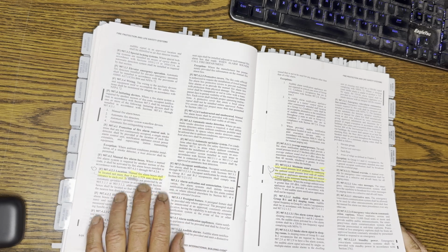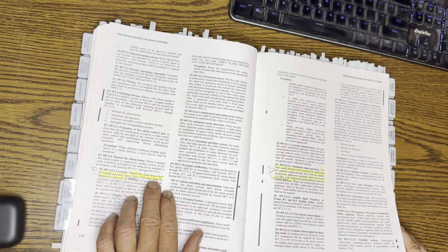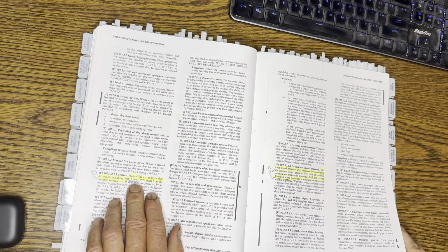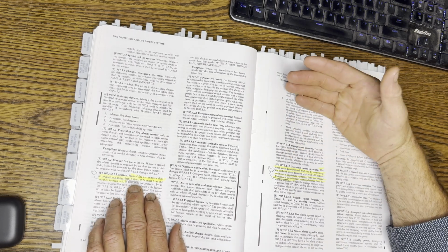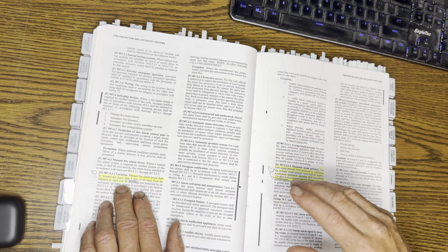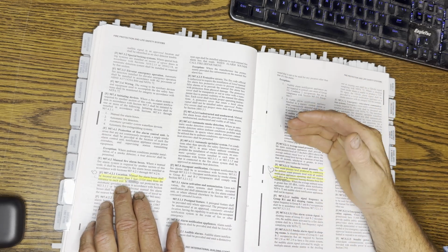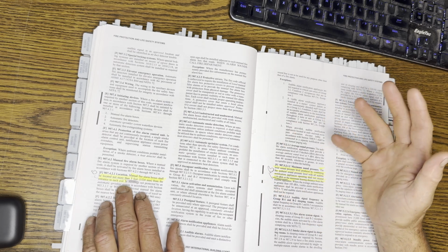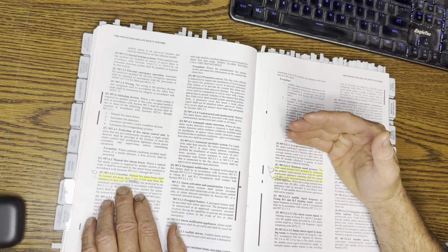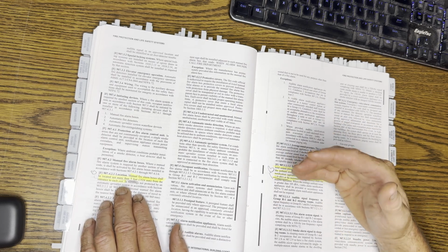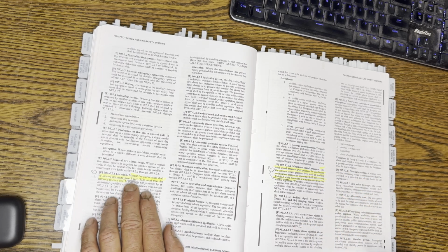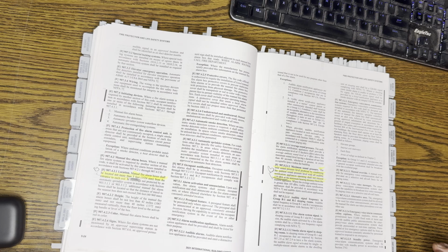Magic number, 5 feet. If you're required to have a manual fire alarm system in a structure, the manual fire alarms have to be within 5 feet of all your exit doors. So just keep that in mind. And that, I want to be very clear, would include not just going outside exit door. Keep in mind the definition of exit is, if you're going into what's called a horizontal exit or an exit passageway or an exit stairway enclosure that's protected by like 1 or 2 or 3 hour rated construction, you've entered into a protected area. So that is considered an exit. So as you go into those locations, you also have to have your manual fire alarm pull station within 5 feet. So just keep that in mind.